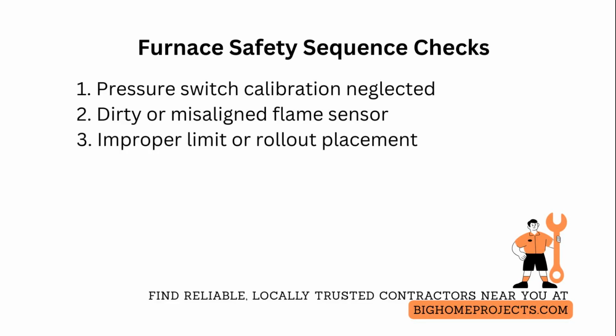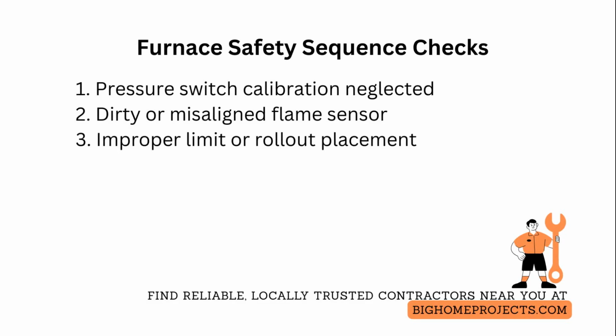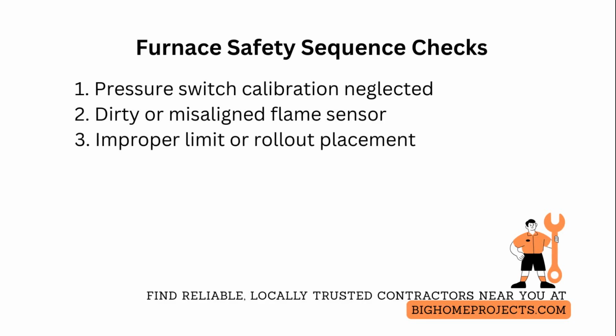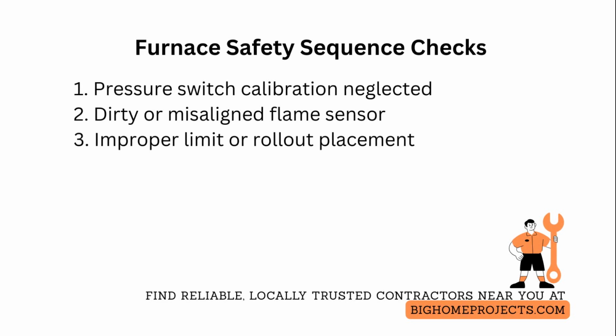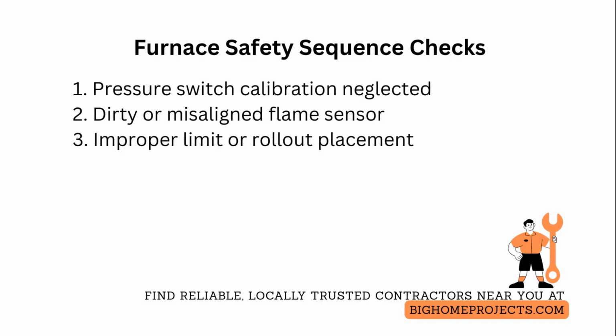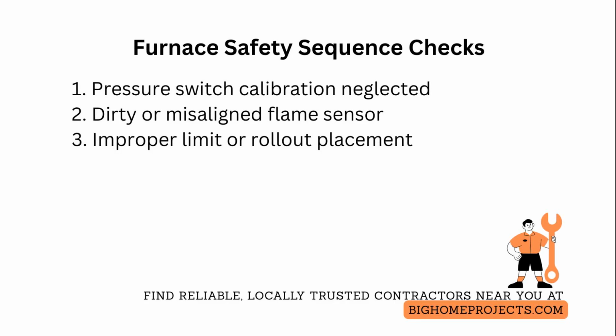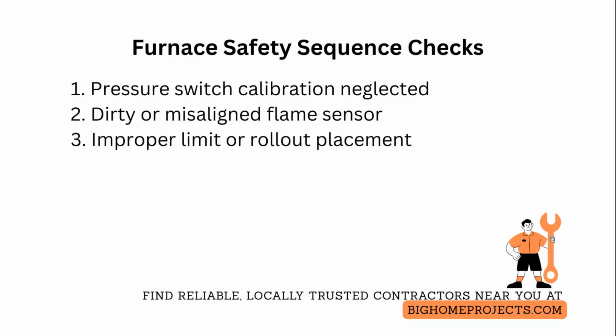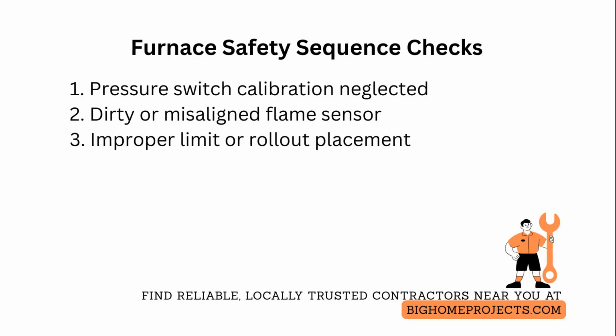One of the most common mistakes is neglecting pressure switch calibration and venting inspection, which leads to blocked vent or false pressure switch faults. Fix this by measuring differential pressure, cleaning or replacing the inducer, and verifying vent paths with a smoke pencil or manometer while confirming proper tubing and tap size to the control board. One of the top errors is relying on a dirty or misaligned flame sensor, causing intermittent flame detection and premature blower activation.